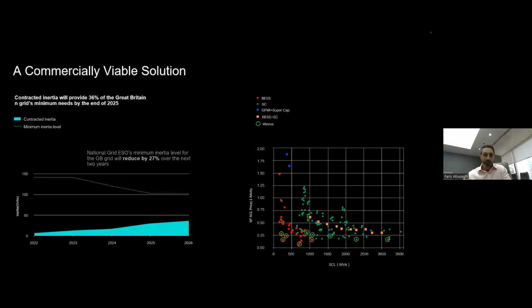So what we've learned as an example, out of experience, they used grid forming batteries as one of the things. They use grid forming inverters, supercapacitor hybrid solutions, even synchronous condensers. They tested different technologies and found that two, grid forming batteries and the synchronous condenser, are the most suitable because they cover bigger or different ranges, and they could compensate for the auxiliary powers of the grid using zero carbon in that sense.